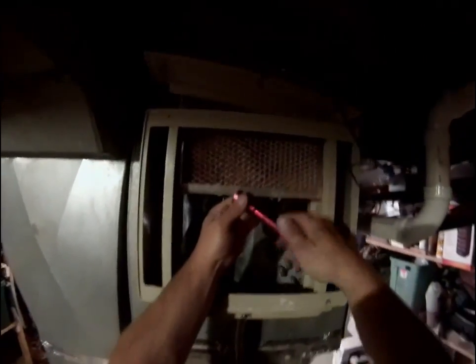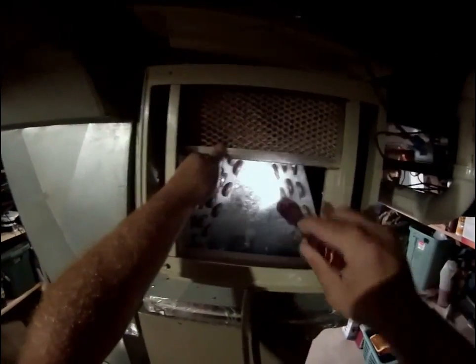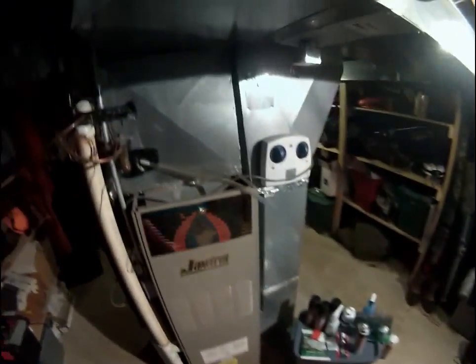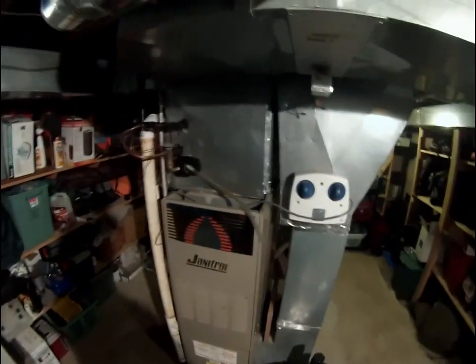So you can take your humidifier apart, and I've kind of taken a lot of the screws out of here. It takes a little bit more time when you're actually doing it. And then typically most humidifiers you're going to see a pad in there of some sort, the drip pad, which we also sell online as well. Set this stuff to the side. So once you pull that pad out of there, then you can see the access. Get a little light on here so you can see the access to the coil from the backside. And again, here's your plate that you take off. Will get you the inside, and you've got outside access to both sides. So again, there's numerous ways you can get at that evaporator coil. And again, during the regular maintenance, in a perfect world, you wanna clean that in most cases.